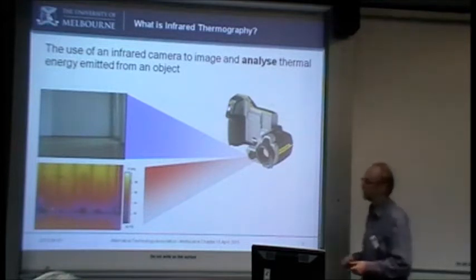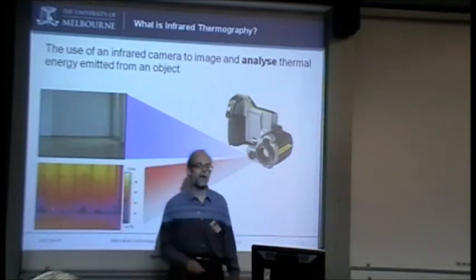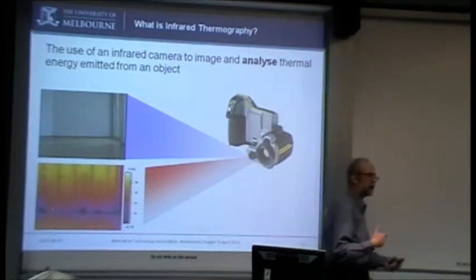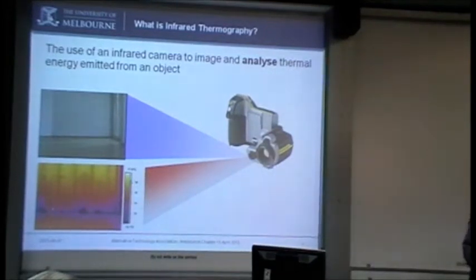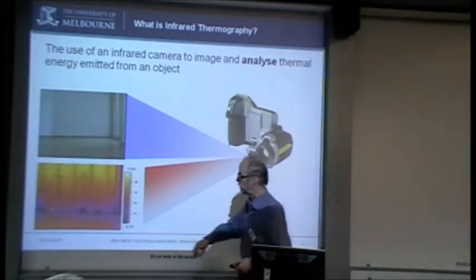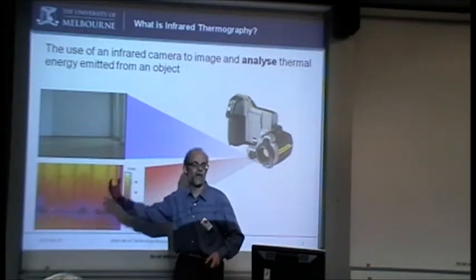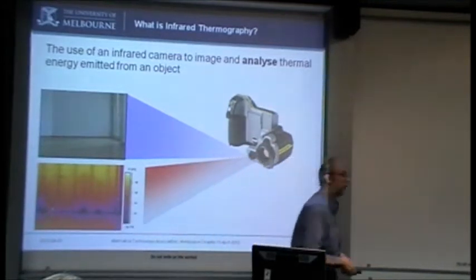And this is a fairly typical sort of pattern that you get when you've got the air leakage. So again, it's partly a matter of experience, much as anything else. This is what we typically see, and so you start to say, well, that's what I've got there. But again, if it was hot outside and cold inside, I wouldn't be seeing this coming in as a dark colour. This would be hotter, so it'd be brighter than the other. So you actually get the reverse.